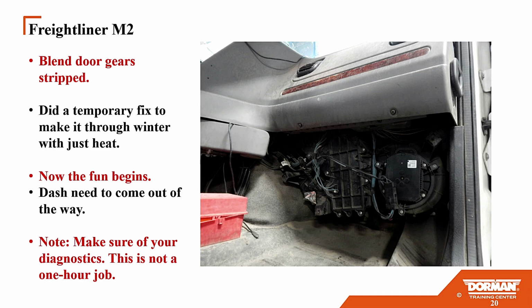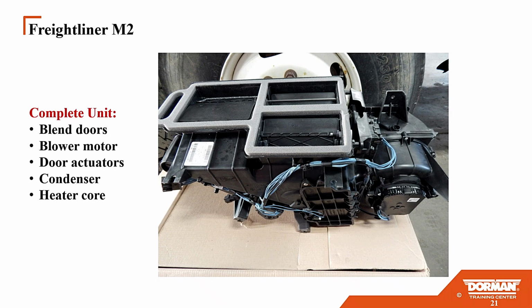Here's an M2 blend door gear strip. This happened in wintertime — a temporary fix to make it through winter with just heat, typical for a fleet. Then it's 'I need the truck' and now the fun begins — now you actually have to do the real fix. This one wasn't just bits and pieces you could swap; the dash needed to come out of the way. So if you're going to do that kind of job, make sure you diagnose first, because this isn't a one-hour job, despite what somebody might say like 'can't you get it done in an hour?' Yeah, right — here's my wrenches, you go for it. This is what you're trying to reach: the complete unit, blend doors, blower motor, door actuator, condenser. I didn't create the problems, so do you want it done right? I'm here, I'll fix it, I'll do whatever, but you have to pay the price. Sorry about that.